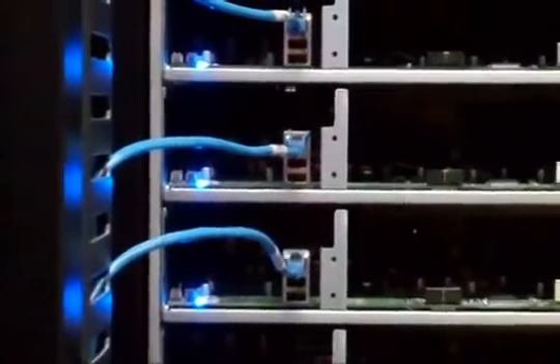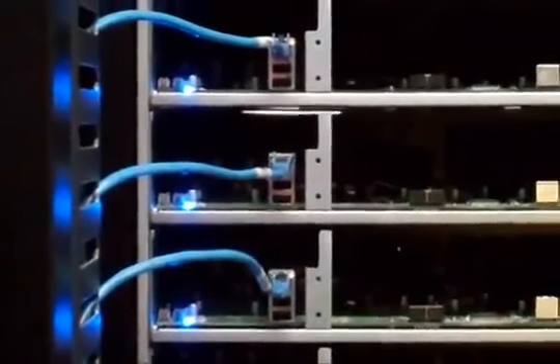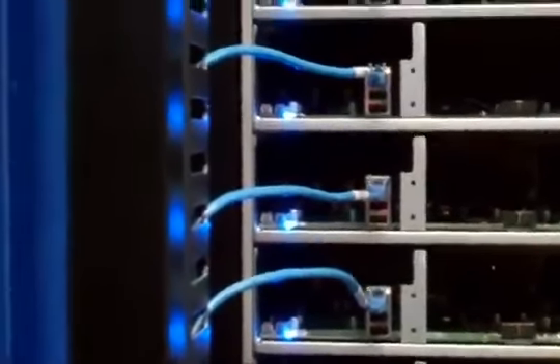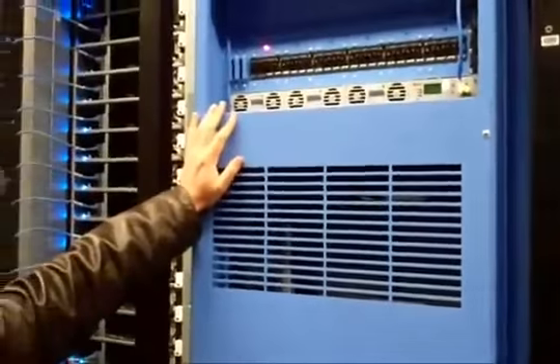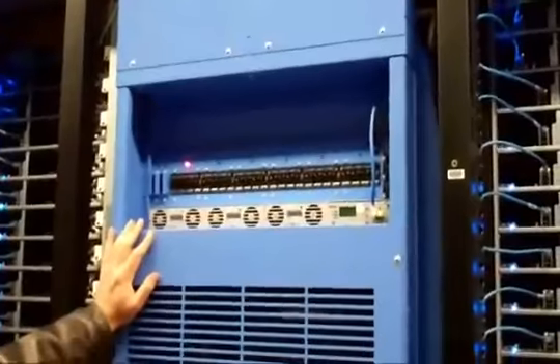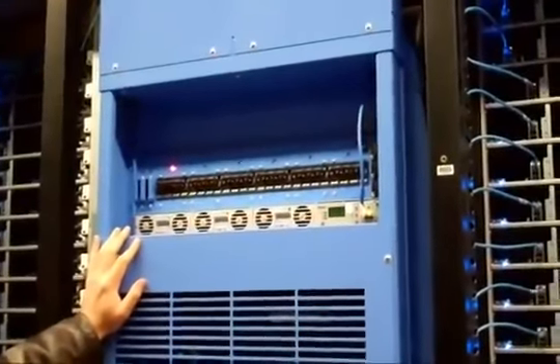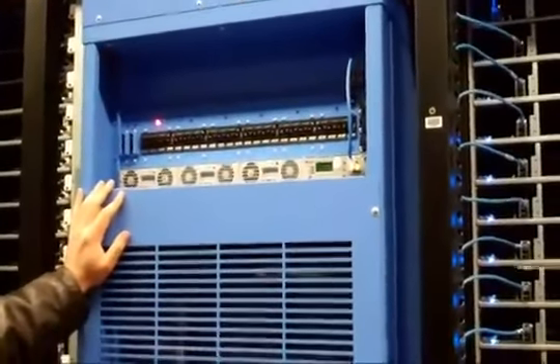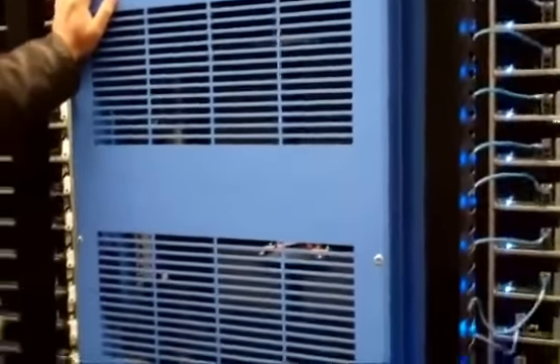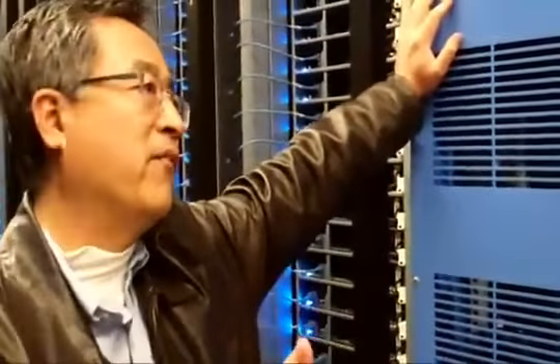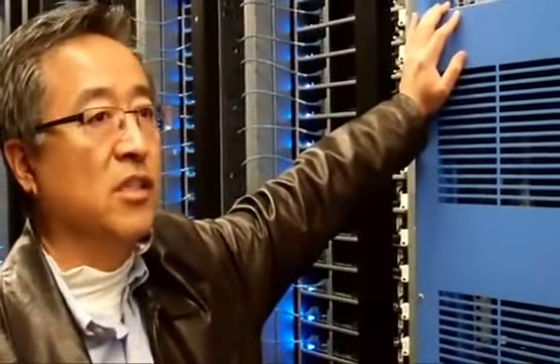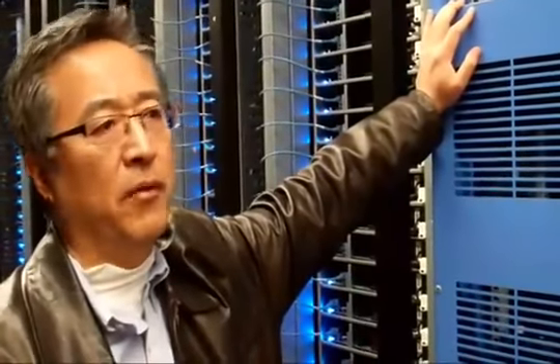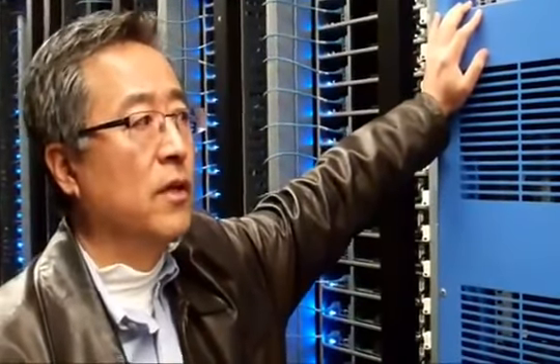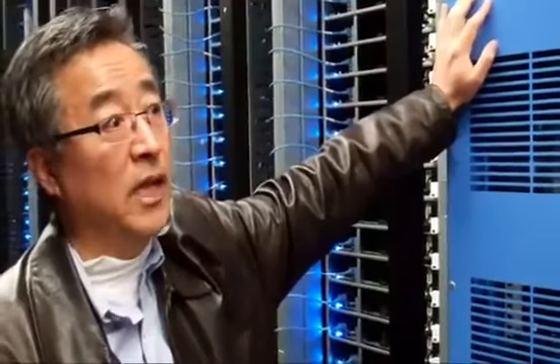If power is interrupted, how long can you run on your direct current? So, good question. This blue cabinet is something we developed as well. This provides up to about 90 seconds. However, we programmed this to only back up about 45 seconds right now, because the emergency generator will kick in within about 15 seconds or so. But this one can handle up to 90 seconds. You're dealing with seconds, correct?